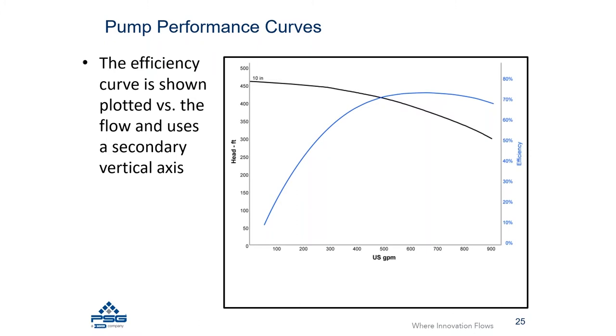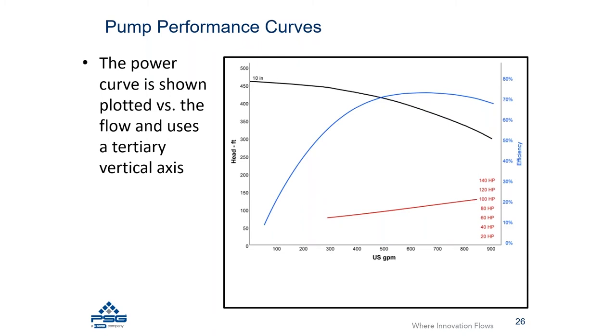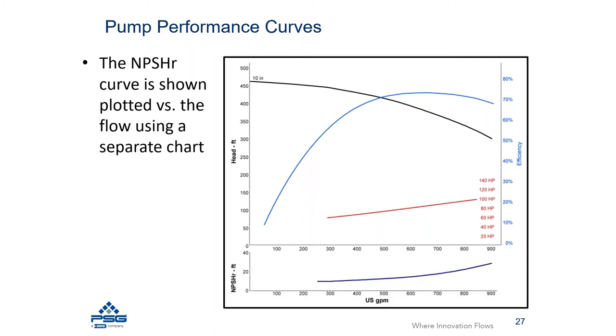You can typically operate the pump further to the right of the best efficiency point, but efficiency will begin to decline. At some point the pump manufacturer will limit the maximum allowable flow rate because efficiency and reliability decline as you move too far to the right. Another characteristic on the performance curve is power, typically presented in horsepower or kilowatts, plotted against yet another axis — shown here in red.